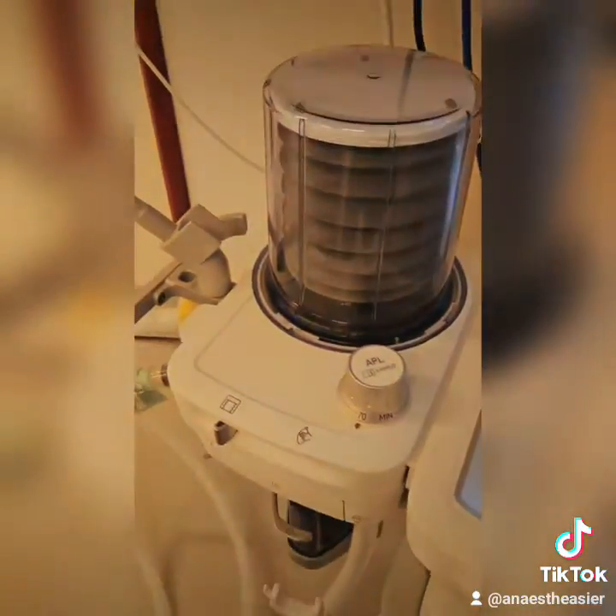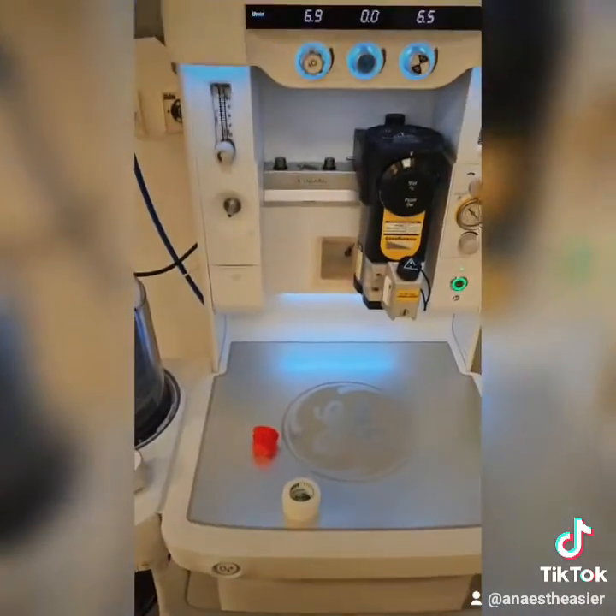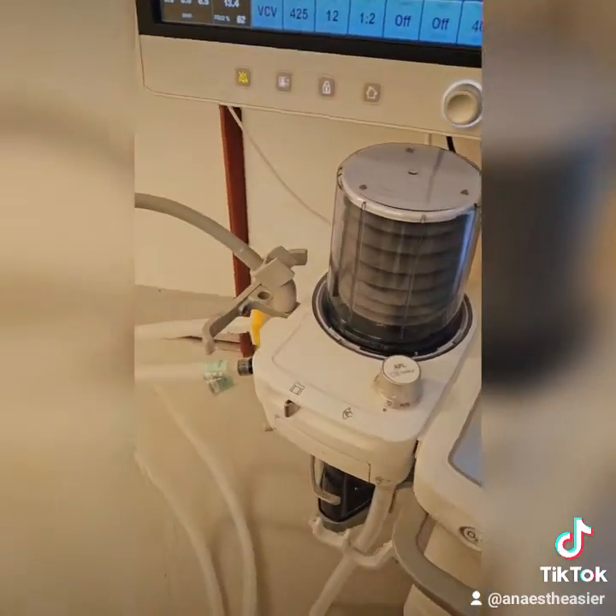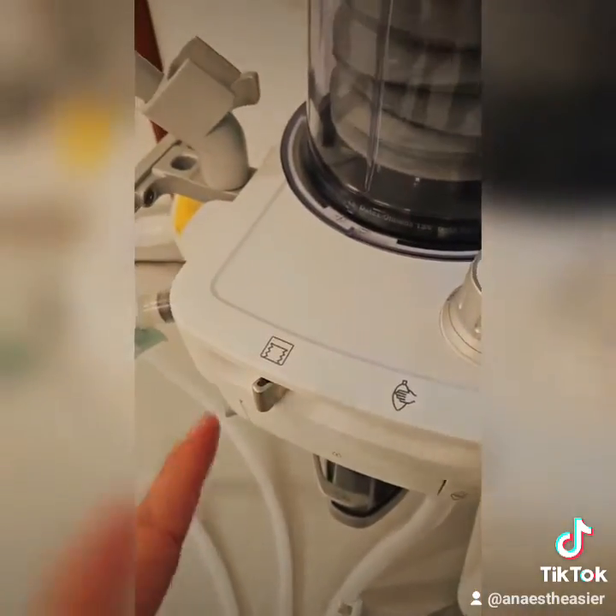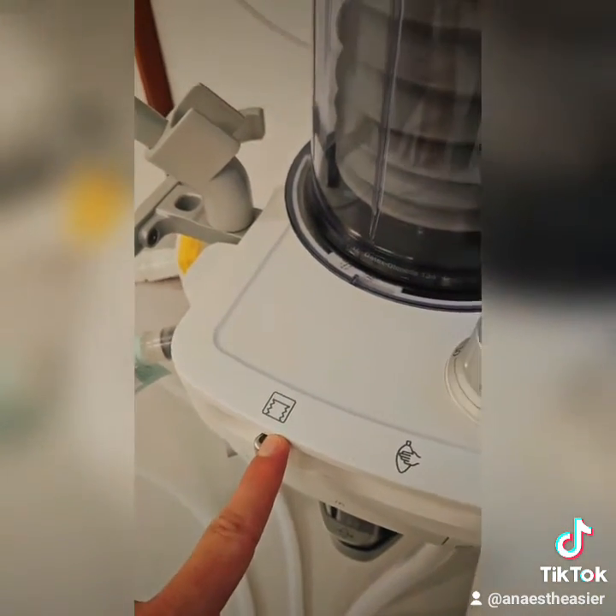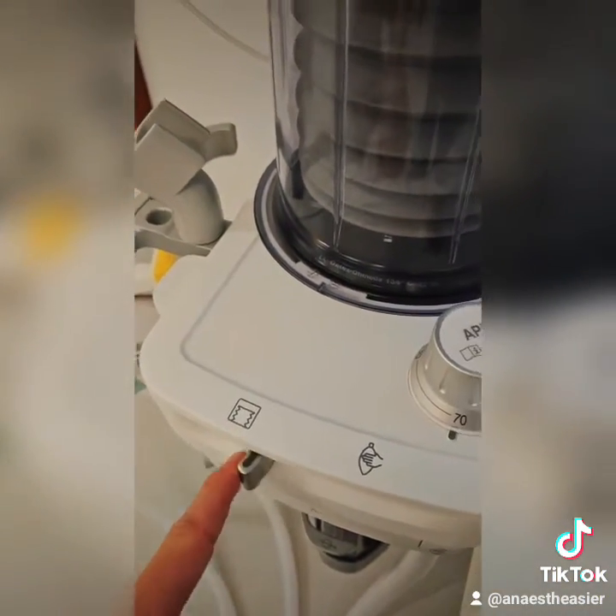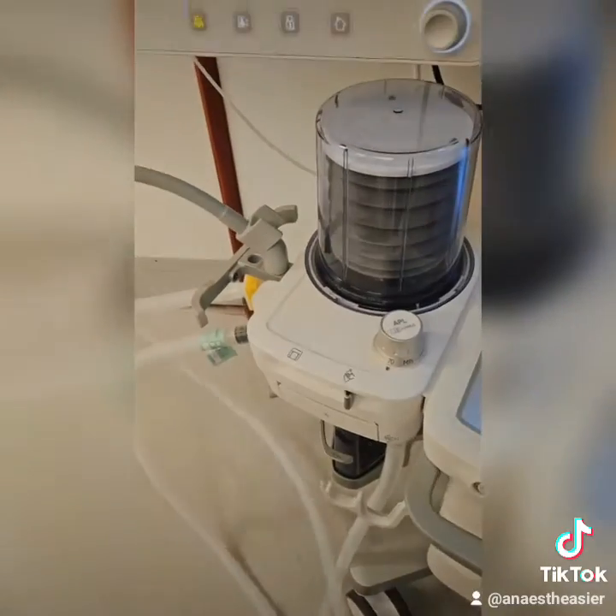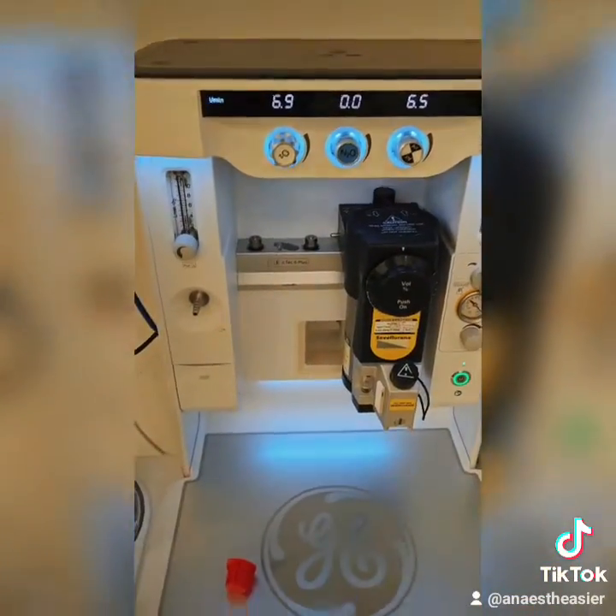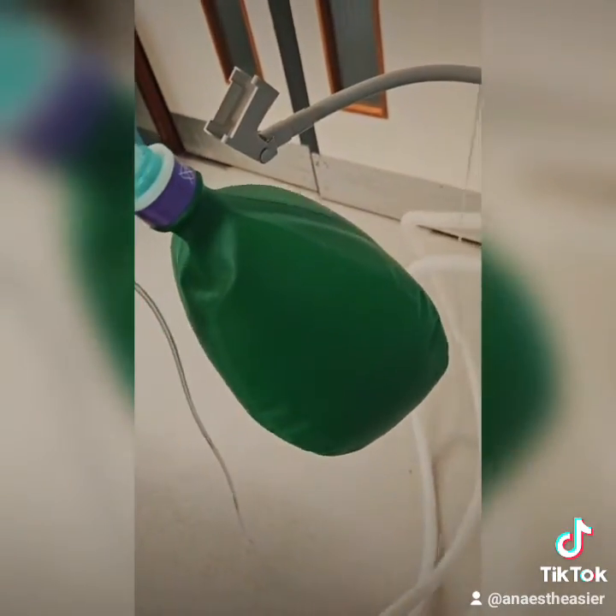So the ventilator is technically separate to an anaesthetic machine, but most anaesthetic machines now come with a ventilator as part of the system. And then you have two options. You can either have them on mandatory ventilation, so this will tell the ventilator to start giving breath, or you can put them on spontaneous mode, which means the anaesthetic machine will still give a flow that you've set through this breathing system, but it won't actively ventilate the patient.